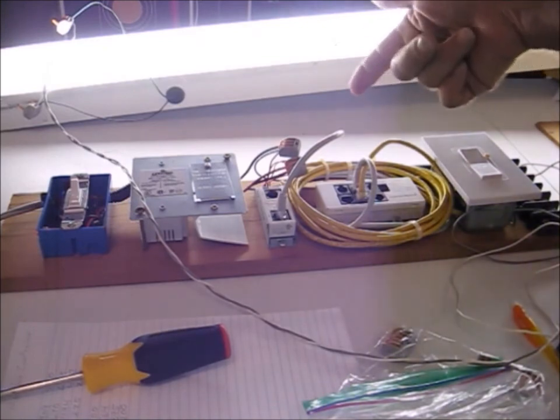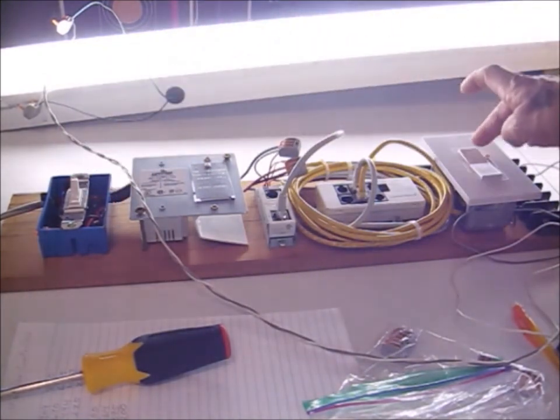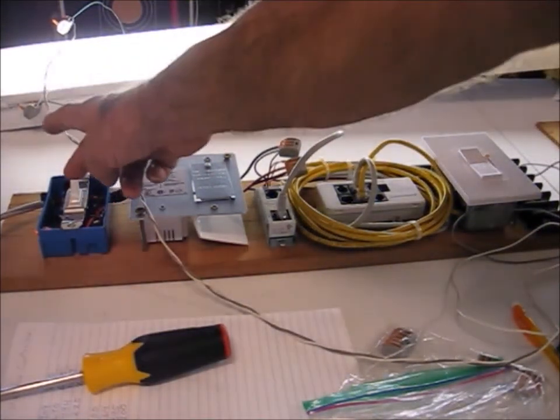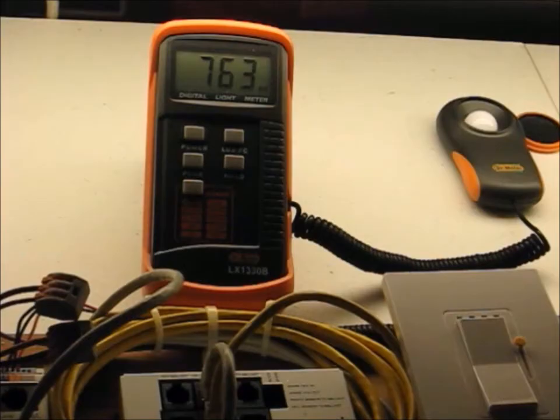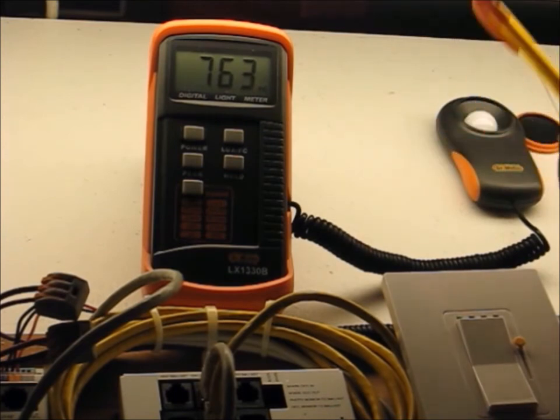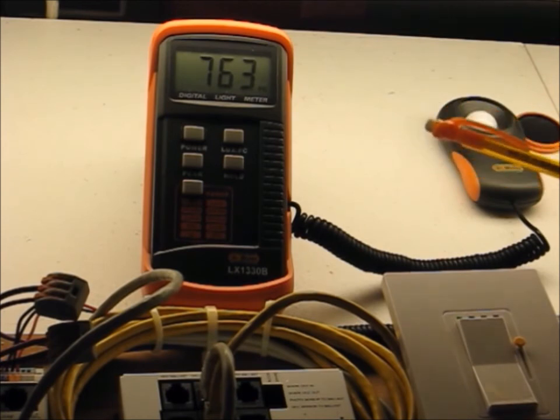Oh, does it respond to losing its DALI bus in a typical fashion? Let's look at that. Yes it does. Now in real life this ballast or LED driver, if that's the case, would be connected to a Lutron power pack known as a PowPak for the Lutron ecosystem or Vive system.